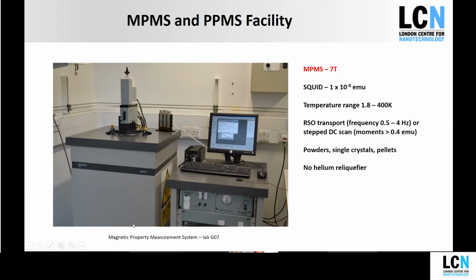So this is a magnetic property measurement system. It has a 7 Tesla magnet. It's actually over 25 years old now, but it still runs fine. It's a high sensitivity SQUID magnetometer with a temperature range of 1.8 to 400 Kelvin. It has an RSO transport, so the frequency is 0.5 to 4 hertz. We can do a DC scan, so we can measure powders, single crystals, pellets. Unfortunately, this one doesn't have a helium reliquefier, so it's extremely expensive to run. So we only cool it down for a large batch of samples to run on it.